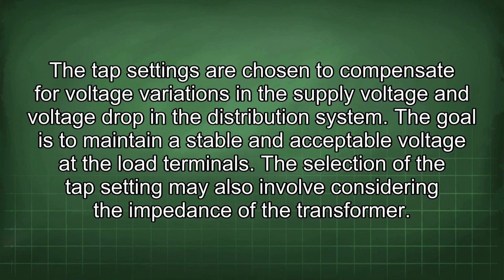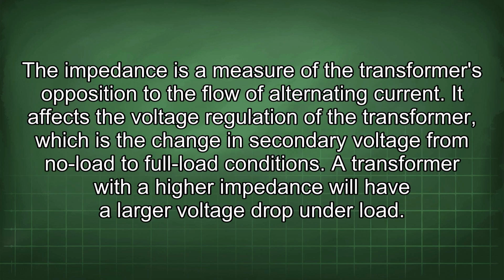The tap settings are chosen to compensate for voltage variations in the supply voltage and voltage drop in the distribution system. The goal is to maintain a stable and acceptable voltage at the load terminals. The selection of the tap setting may also involve considering the impedance of the transformer. The impedance is a measure of the transformer's opposition to the flow of alternating current. It affects the voltage regulation of the transformer, which is the change in secondary voltage from no load to full load conditions.